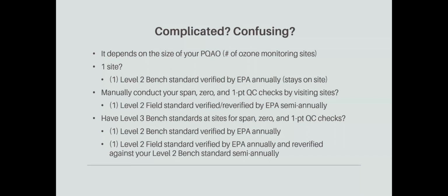your ozone traceability. Here at ARS, since we're a consultant, we're basically an extension of a variety of different PQAOs. And we have 2 bench level 2s, because we have one that's for our maintenance and calibration group, and we've got one for our audit group so that we can be independent. Under the maintenance and calibration group, we now have 6 level 2 field standards to take to the field, and we only have level 3 bench standards in the field. And on the QA audit side, I mentioned the level 2 bench, and then we have 2 level 3 field standards.